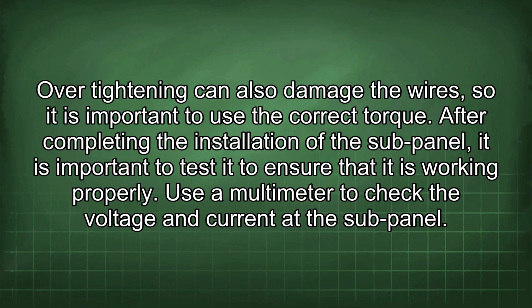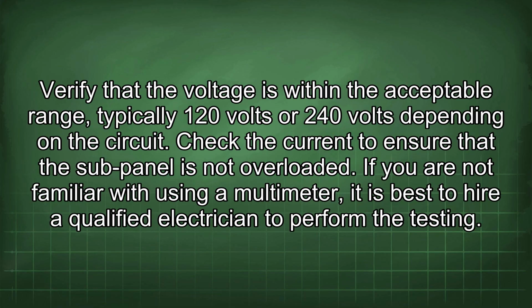After completing the installation of the sub-panel, it is important to test it to ensure that it is working properly. Use a multimeter to check the voltage and current at the sub-panel. Verify that the voltage is within the acceptable range, typically 120 volts or 240 volts depending on the circuit. Check the current to ensure that the sub-panel is not overloaded. If you are not familiar with using a multimeter, it is best to hire a qualified electrician to perform the testing.